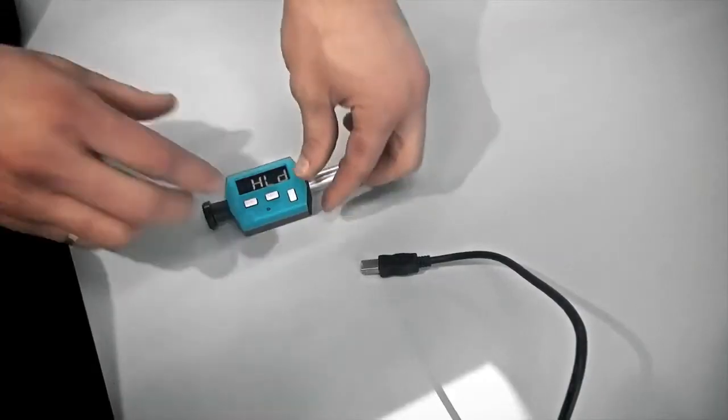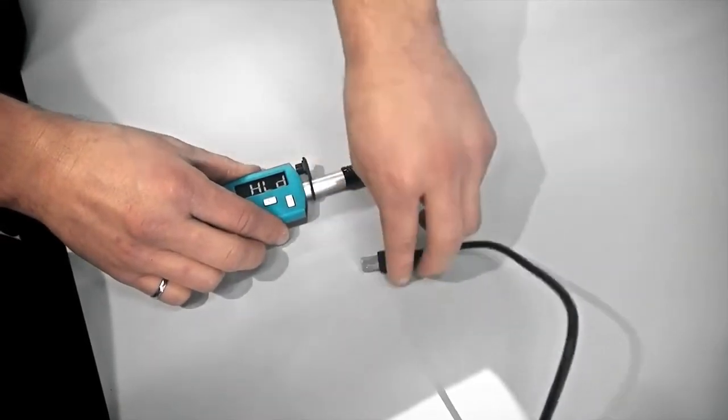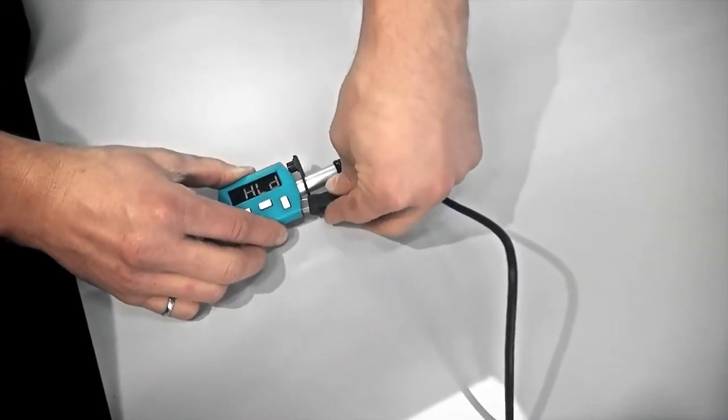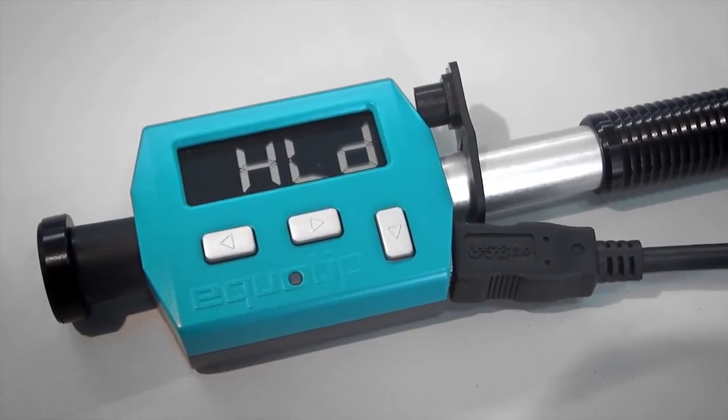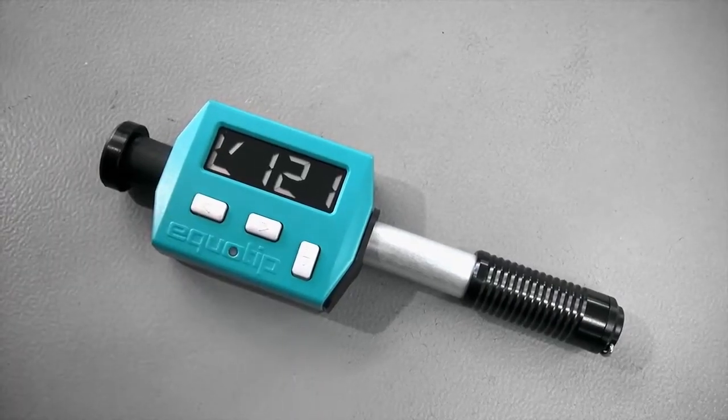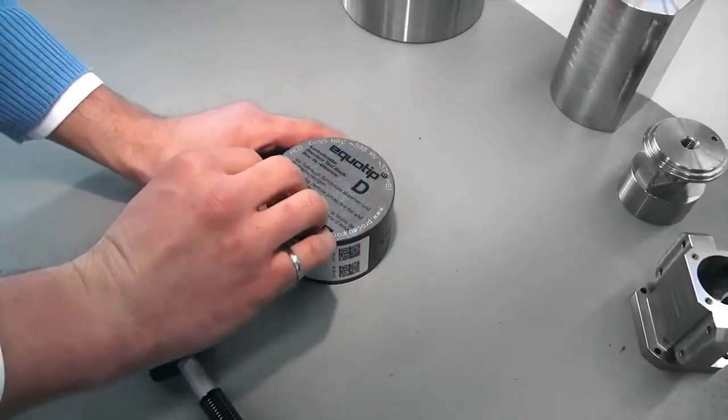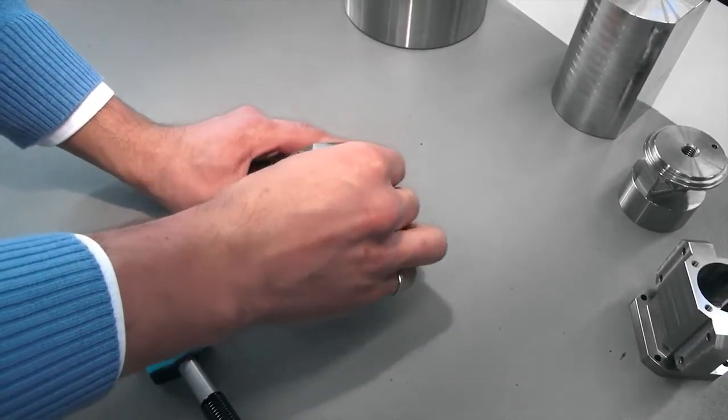Before using the instrument, please make sure the battery is charged. When fully loaded you can make at least 20,000 measurements. To turn the instrument on, press any key. When you use the instrument for the first time, the Leeb is the default hardness scale.